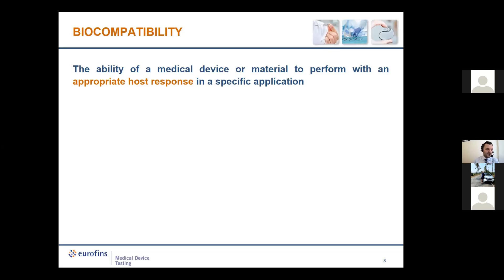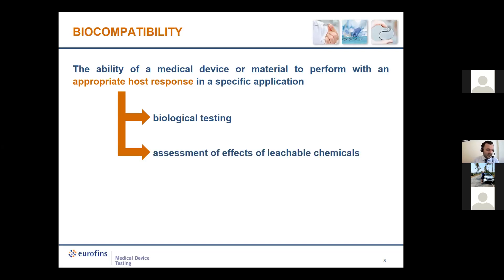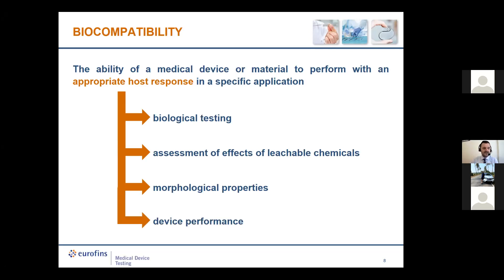The term 'biological evaluation' is sometimes used interchangeably with 'biocompatibility.' From Part 1, the definition of biocompatibility is: the ability of the medical device or material to perform with an appropriate host response in a specific application. These properties are assessed by performing biological tests and/or evaluating the effects of leachable chemicals. Biocompatibility is also linked to the morphological properties of a medical device and — perhaps most relevantly — to the performance of the medical device. When dealing with biocompatibility, we have to think in a holistic way.